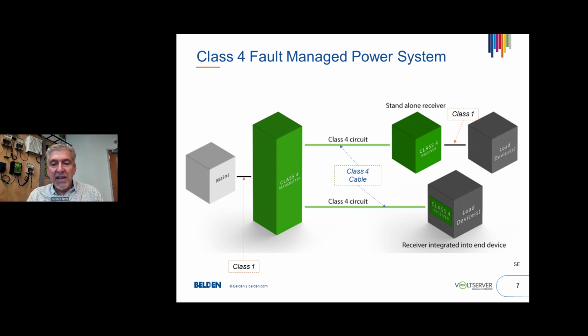But electricity hasn't migrated as quickly to the digital world. So fault managed power is a flexible, rapid installation process that combines data and power in the same cable. As Ron was talking about cable types, many of those cable types will also contain fiber, or they can contain communications copper in the same jacket. So this is all about a combination of power and data in the same channels that installs very quickly, like Class 2. So the main components are transmitters and receivers.